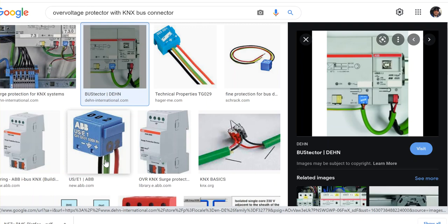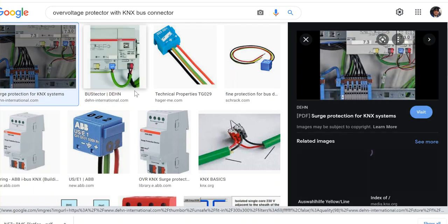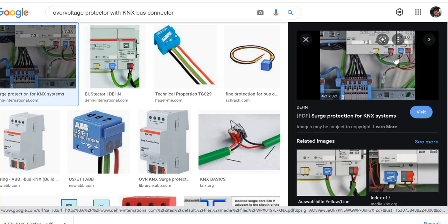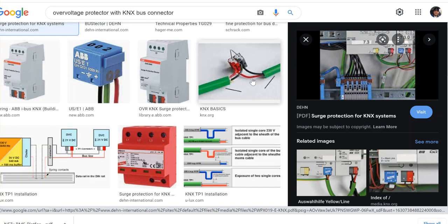But remember that as a surge arrestor, you should have the primary in your main electrical board and use this one as a secondary one. But where do we connect it? You can connect this to the line coupler or power supply in each line. So each line has its own secondary surge arrestor or lightning protection KNX connector. For example, this is a primary surge arrestor. You can see it in the book, in a Google search, and this is the secondary one in KNX.